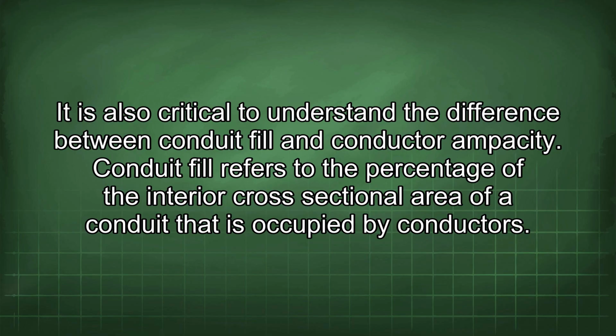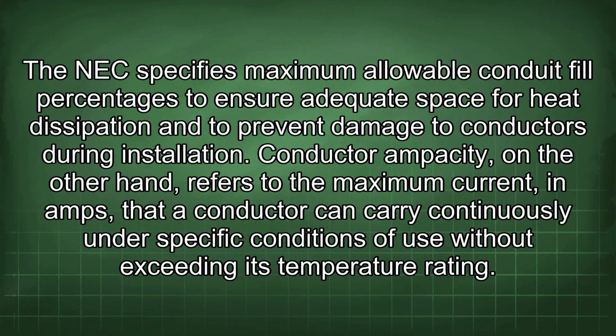It is also critical to understand the difference between conduit fill and conductor ampacity. Conduit fill refers to the percentage of the interior cross-sectional area of a conduit that is occupied by conductors. The NEC specifies maximum allowable conduit fill percentages to ensure adequate space for heat dissipation and to prevent damage to conductors during installation. Conductor ampacity, on the other hand, refers to the maximum current in amps that a conductor can carry continuously under specific conditions of use without exceeding its temperature rating.